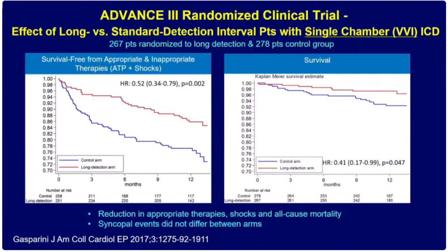So if you notice, on the current devices, you have not just all these discriminators and rate cutoffs and all these other number of intervals to detect, but you also have what is being referred to as modern programming strategies. So there are things like novel discrimination, T-wave oversensing algorithm, lead noise. The engineers are very smart. They can have the device be able to detect the difference between noise and other things. RV integrity alert, and including all those different features in there too.